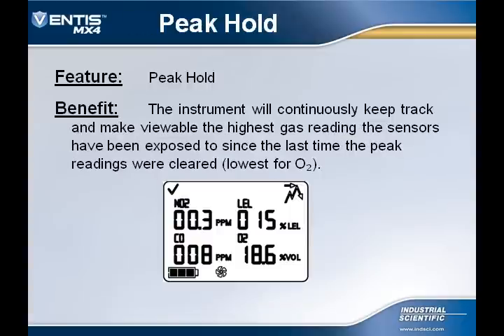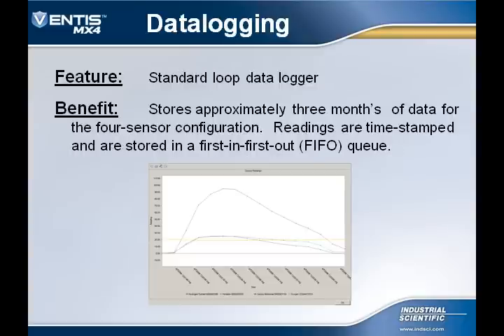The Ventis MX4 records your peak readings. This means that the unit records the highest readings for toxic and the lowest for your oxygen since the peaks were last cleared. The Ventis has a standard loop data logger, capable of storing 3 months of data for the 4-sensor arrangement. Once the data logger is full, new data logged will overwrite the oldest data in memory.